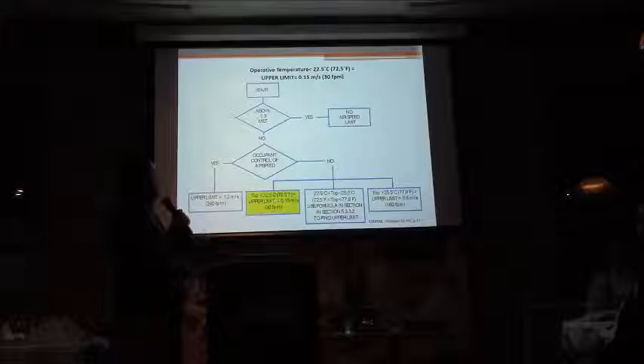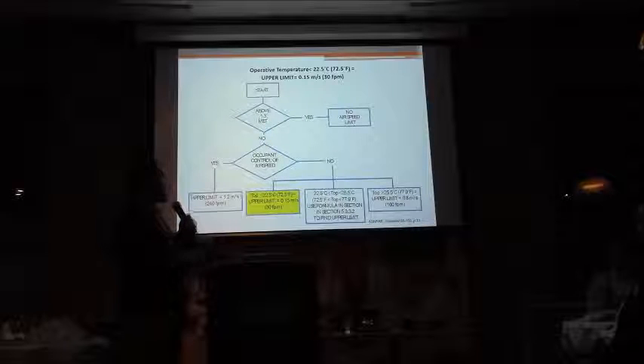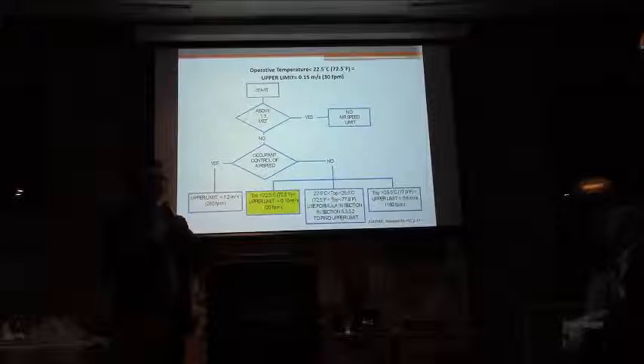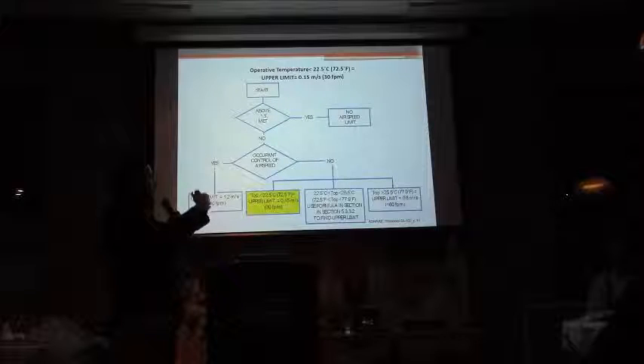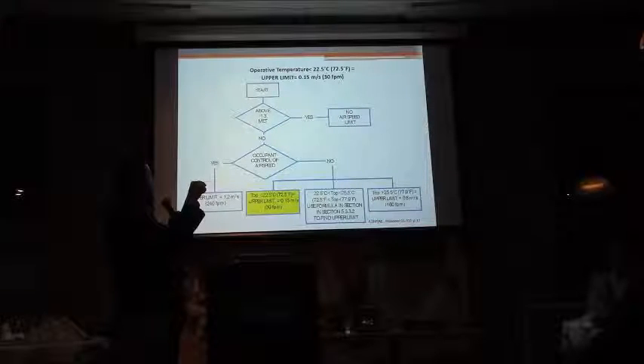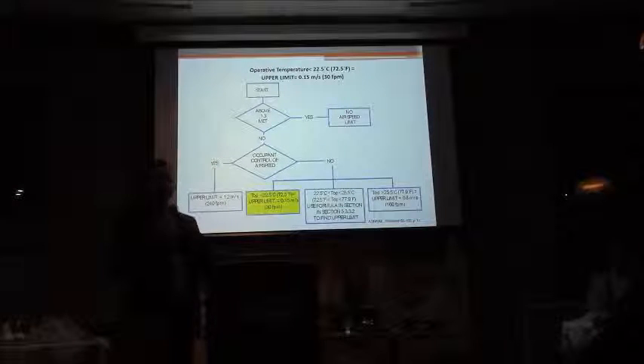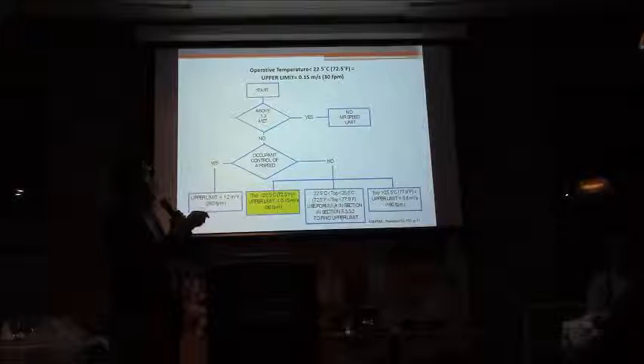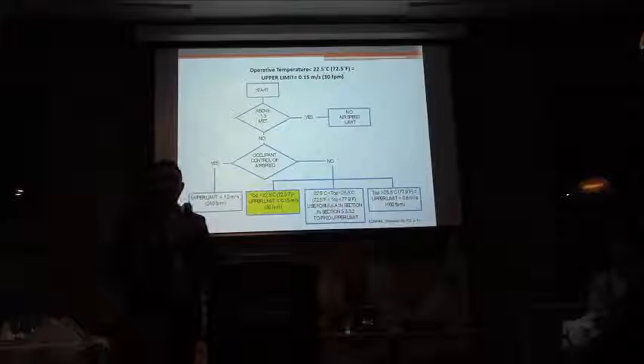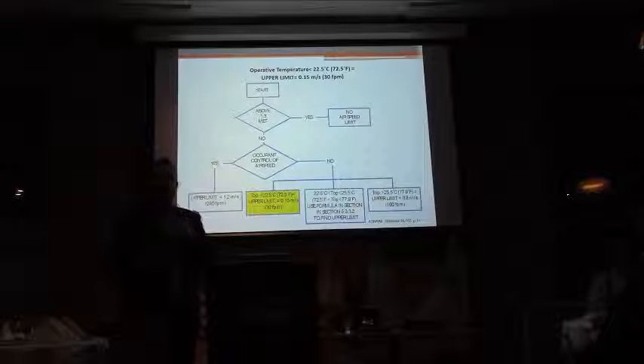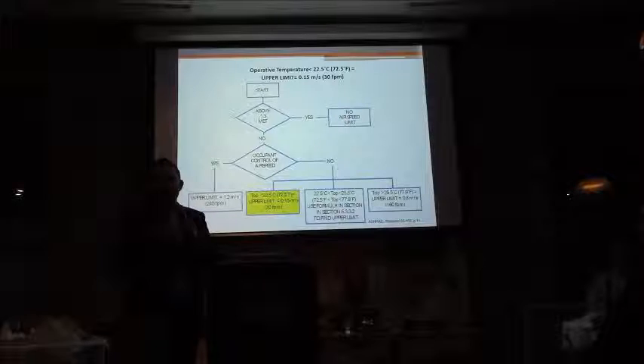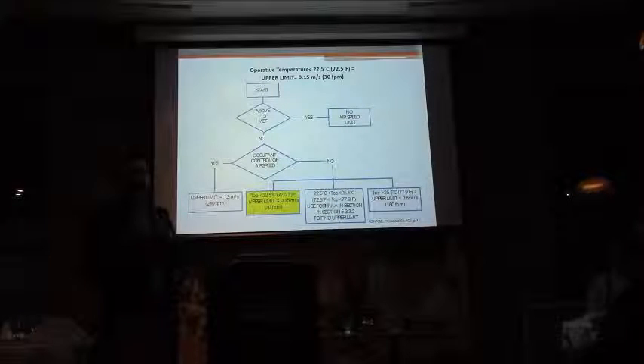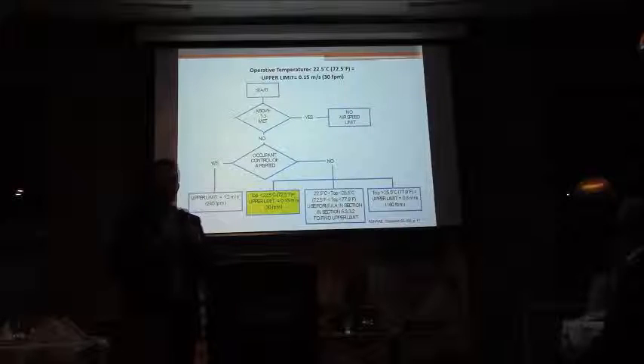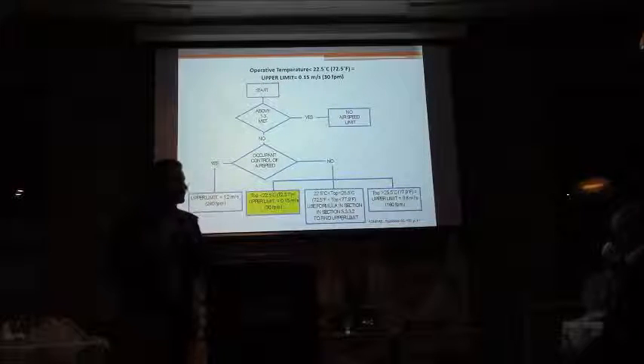So this one here is a flow chart. You find it in ASHRAE 55, page 11. Basically, it sums up everything I just said, but in more of a flow chart kind of graph. So you start here, it asks you, what's your metabolic rate? Are you above 1.3? If the answer is yes, then you're not designing an office application. You're probably designing something like a gym, and you don't have a maximum airspeed limit. If you go to the gym and you're running on the treadmill and you're hot, getting a draft of cold air actually feels good. It doesn't bother you much. The most sensitive applications are office type applications where your metabolic rate is very low.